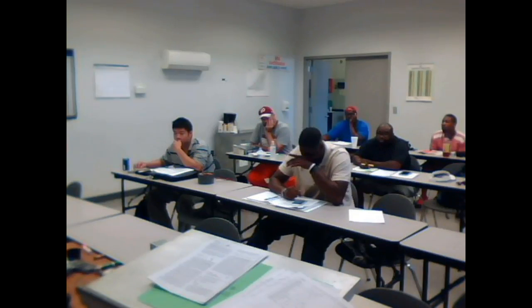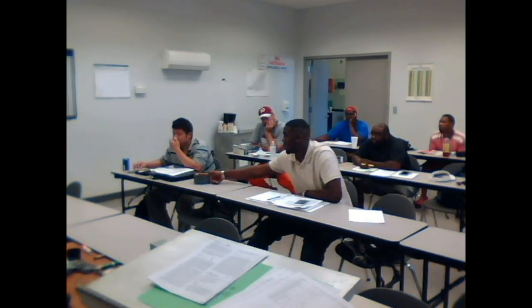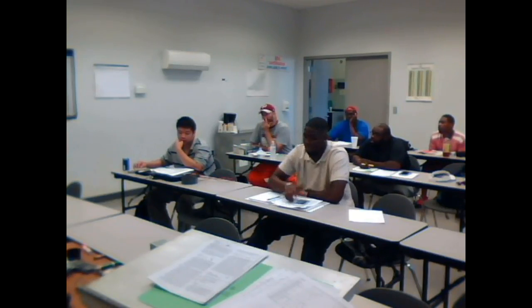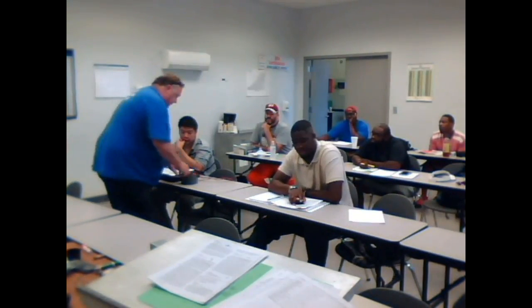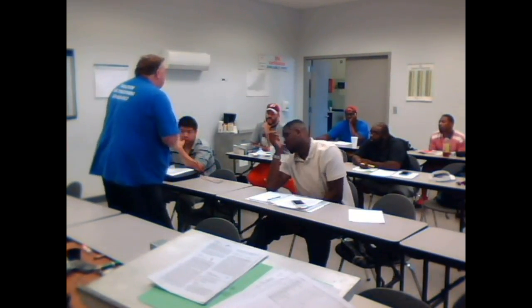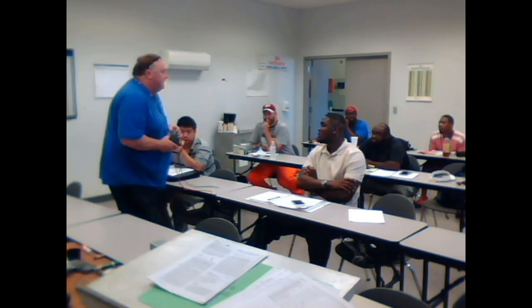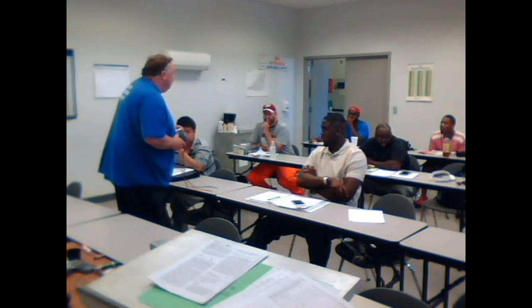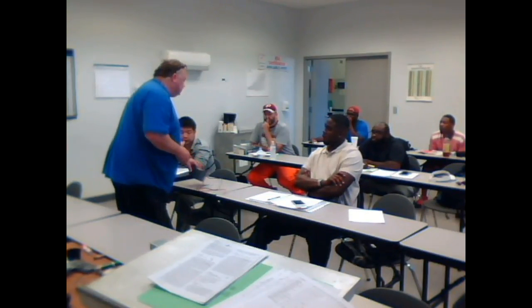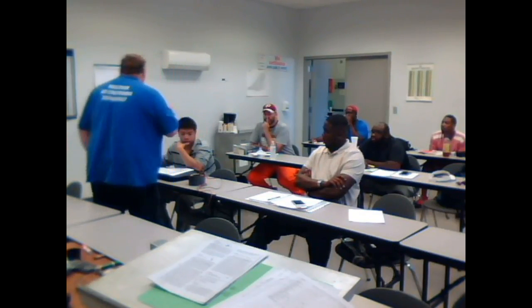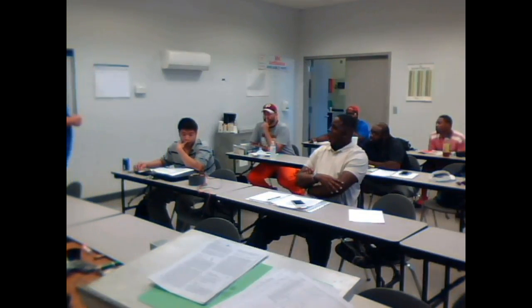We got an overload in there. If it gets too high, we'll cut it off. Y'all look at this. Right here on the coil, there's this little silver rectangular box. That's our overload, and it sits in amps. If this thing gets too hot, it's going to cut it off, and when it cools off, it'll close back down and let the power flow through it.